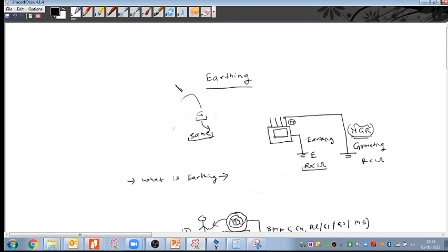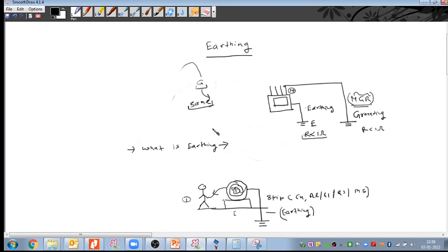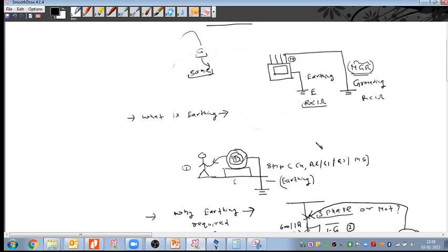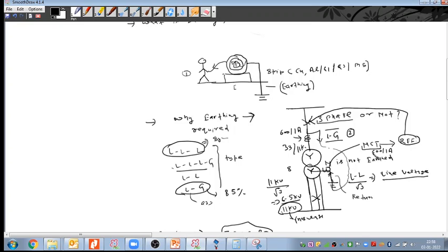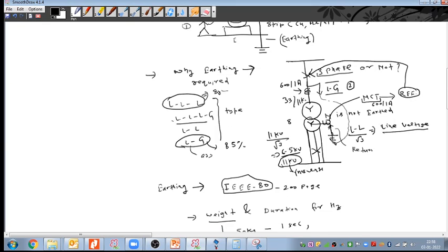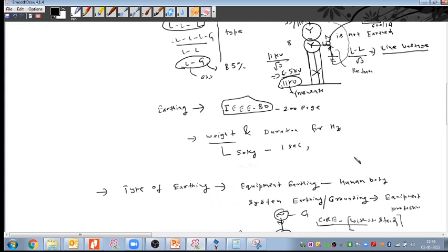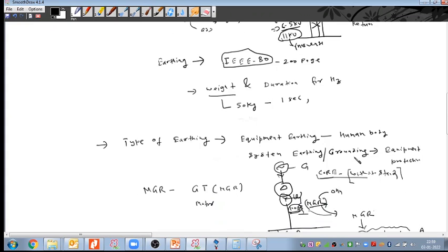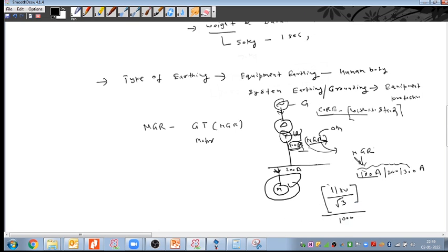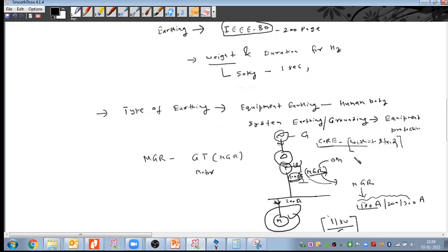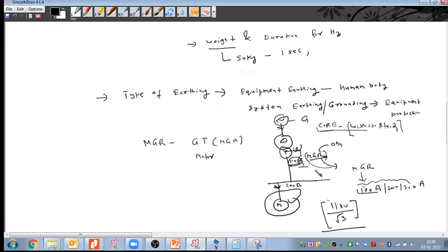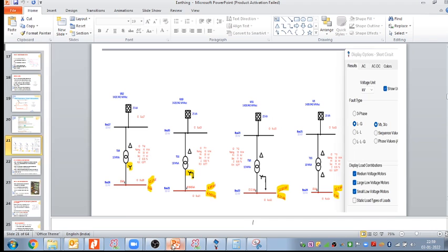We discussed the difference between earthing and grounding. Then what earthing is, and the types of earthing. If it is an ungrounded system, what is the drawback? And the current that comes when we talk about grounding is the line to ground fault current. We discussed how much current a person can tolerate, the tolerable body current IB, that is 116 milliampere, 157 milliampere. We discussed which one is dangerous, AC. Then types of earthing: solid earthing and NGR earthing, and we did some comparison between solid and NGR earthing. We calculated the NGR value based on how much current we want to allow. Now in the next session we'll discuss the remaining part.